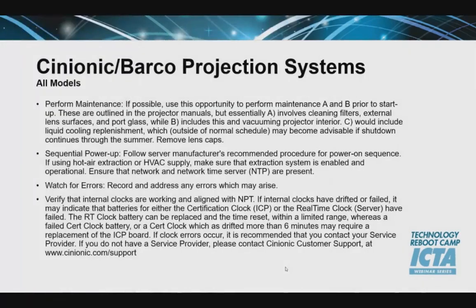So at this point, we'll move on to Cinionic Barco. Cinionic Barco touched on the fact that this is a prime opportunity to get as much preventative maintenance done as possible. The theaters are empty, so there's no better time than now to perform maintenance, get filters clean, get lens surfaces clean, clean port windows, vacuum out the projector completely, and really go through a full calibration of everything from top to bottom.